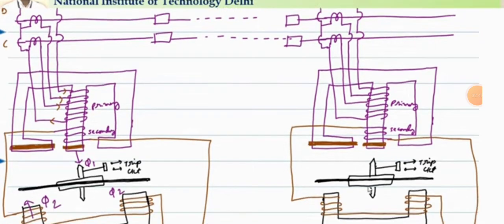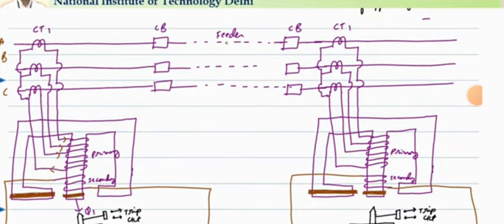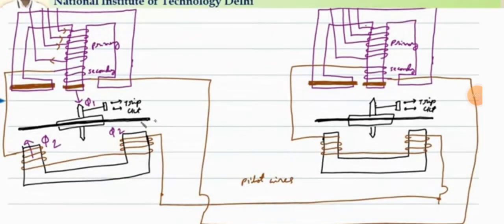The shading ring in the side limb provides the required restraining force which depends on the fault current, taking care of the effect of mismatch in CT characteristics. When a fault happens internal to the protection zone, there is a difference in the CT currents from both sides, so the secondary induced EMFs are disturbed and circulating currents pass, operating the relay depending on whether it is a singly-fed or doubly-fed system.